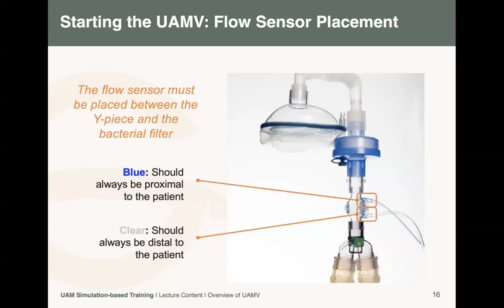So as we have said, we have two machines. First one, we have this one, whereby you have all the ventilator drive hose, and then you have the normal flow sensor tubes, the blue one and the clear one. And the hose is always attached on the vent, and also goes down on the breathing block. This is very important because if it's not connected, you always create a leakage in the system, and you end up with the issues.